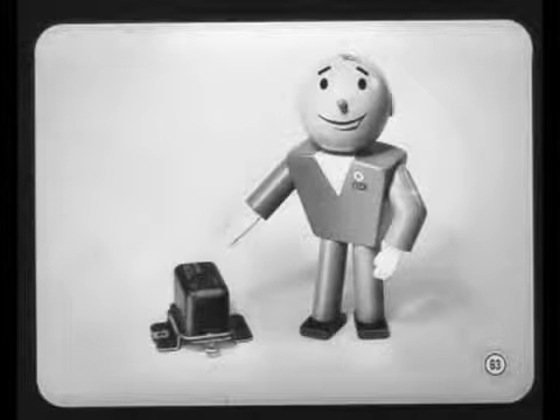Measured 2 inches from the regulator cover after the warm-up. Remember that the cover must be in place for all regulator tests. And one more thing: be sure to cycle the regulator before you take each test reading. The easiest way to do this is with a handy little cycling switch you can make for yourself. The service manual tells you how. Want to take it from here, Larry?